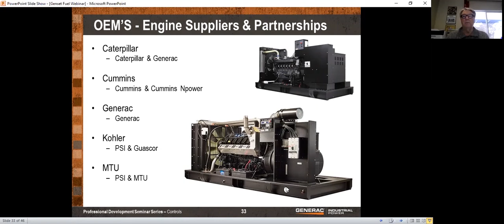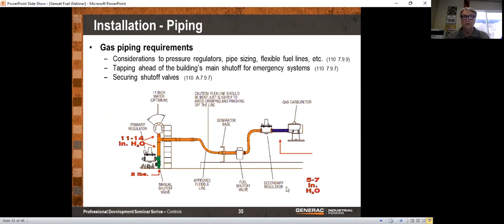Gas piping requirements. We need to make sure that you have a gas pipe that can deliver the appropriate quantity of natural gas. We generally recommend that you have 10 feet or more between the step down regulator for natural gas and the generator, and that just gives you a little bit of natural gas storage in there to assist you in getting a reliable start.